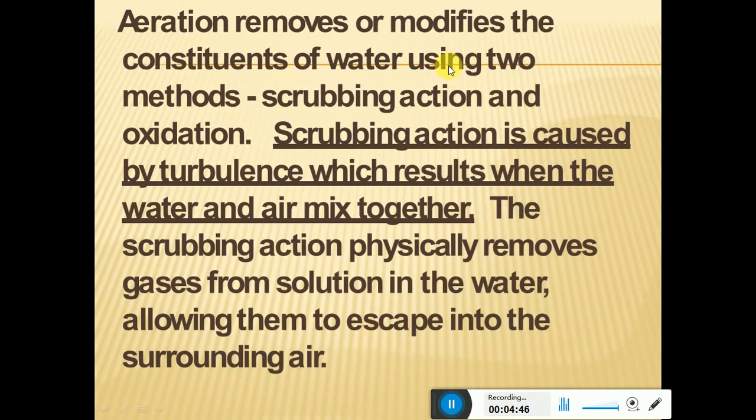So here aeration removes or modifies the constituents of water using two methods, that is scrubbing action and oxidation. So scrubbing action is caused by turbulence, which results when the water and air mix together. So we create a condition so that the turbulence occurs, okay, whenever the aeration process takes place. So this scrubbing action physically removes the dissolved gases from the solution in the water and allows them to escape into the surrounding air.